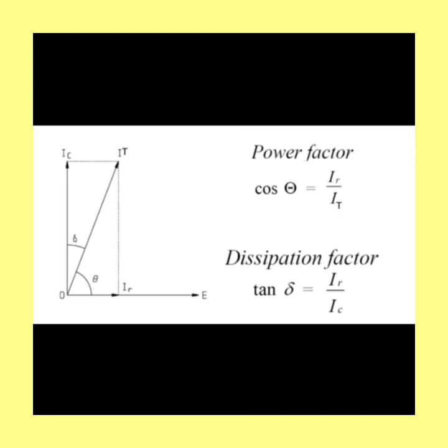And the permissible capacitance variation allowed with respect to the capacitance provided at the time of testing in the lab of manufacture should not vary plus minus 3%.